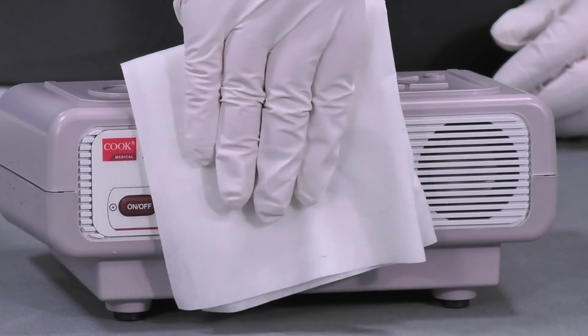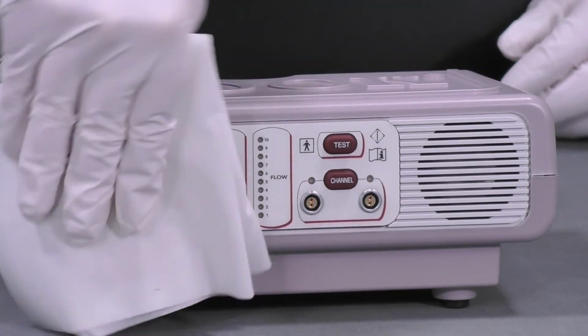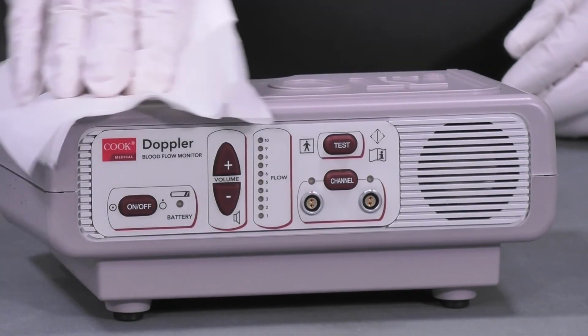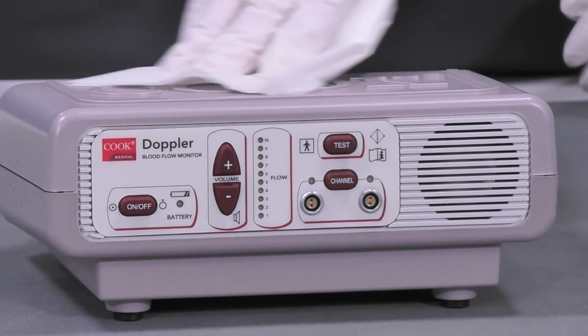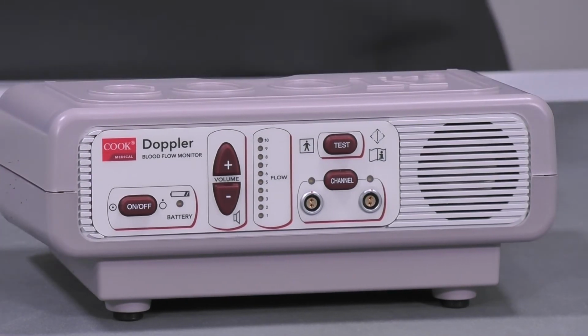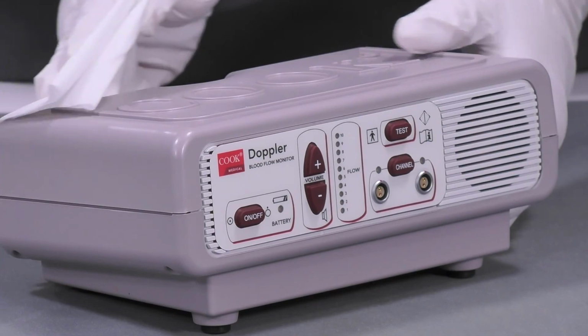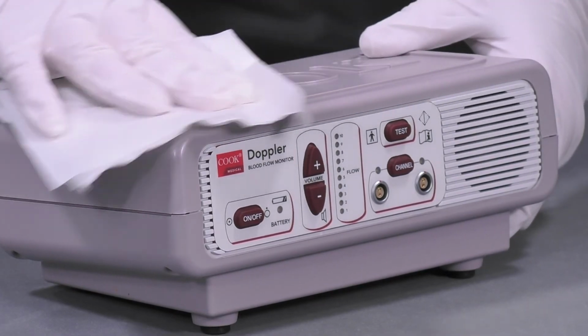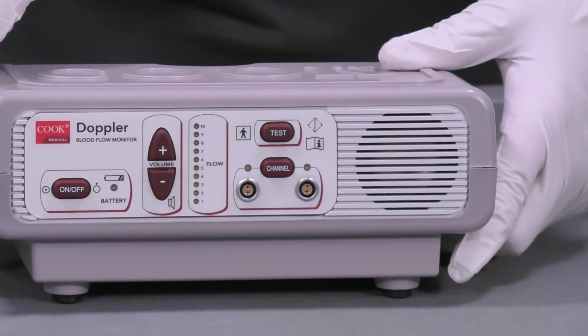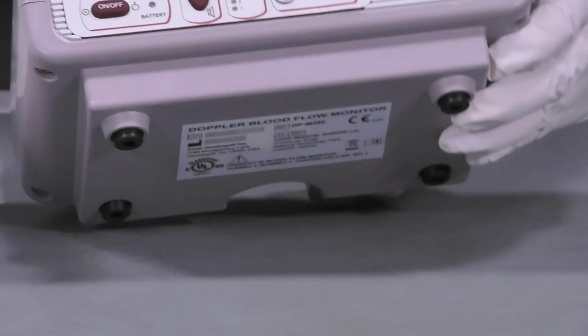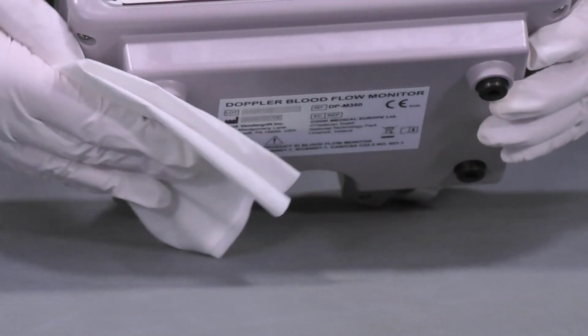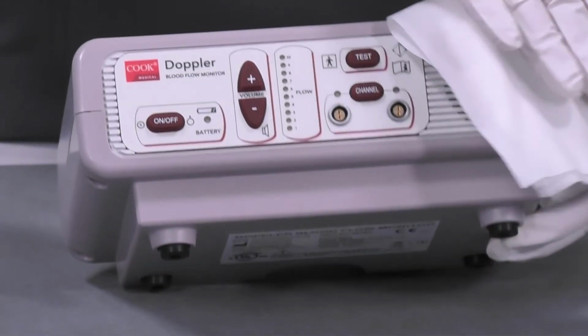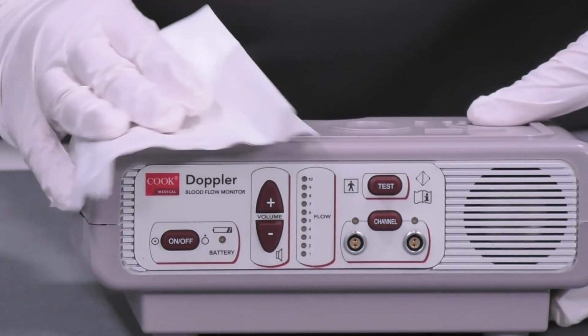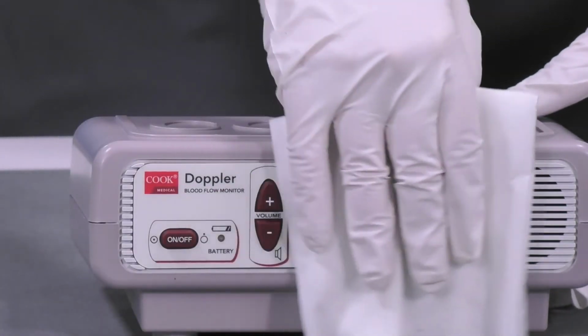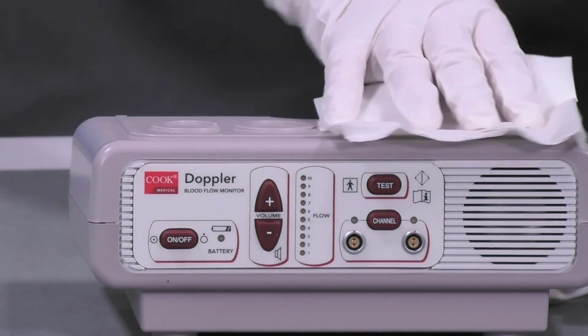Before cleaning, make sure that the monitor is not connected to a power supply. Do not immerse the unit in solution or allow solution to enter the connector inputs, outputs, or the speaker grill. Be sure that the unit is completely dry and tested following each cleaning and before each use. Do not sterilize. The monitor and the channel cable verifier may be cleaned with a mild detergent or isopropyl alcohol.